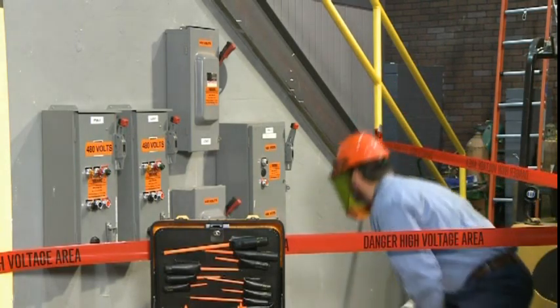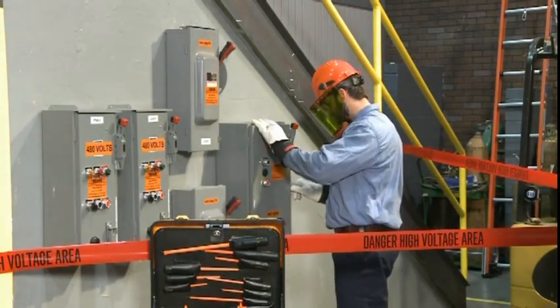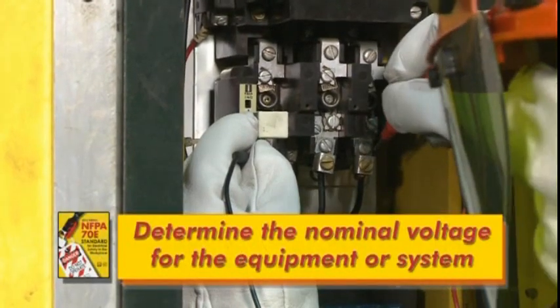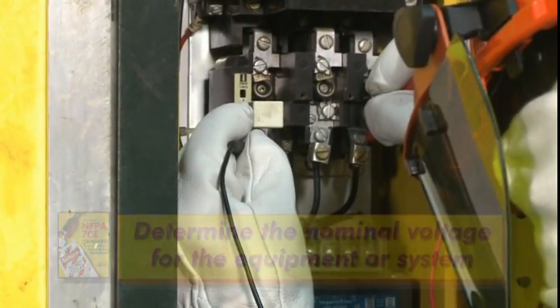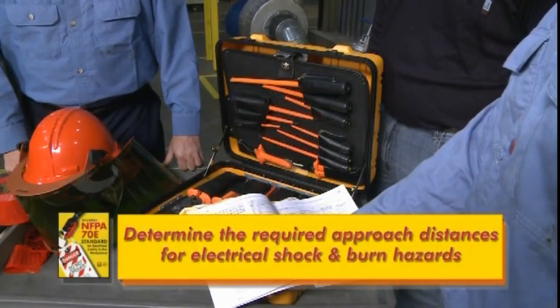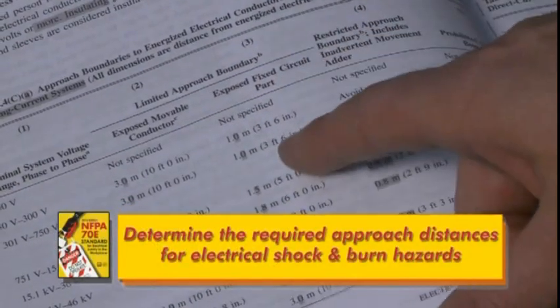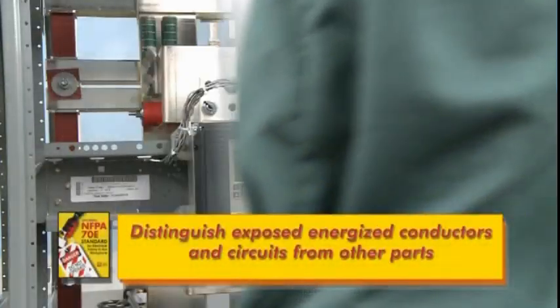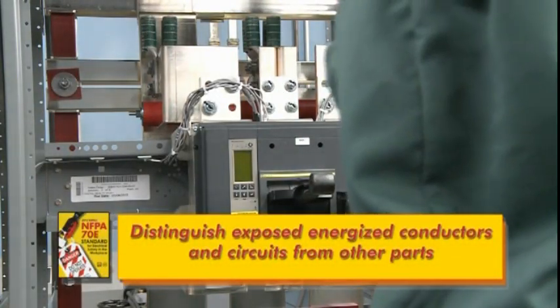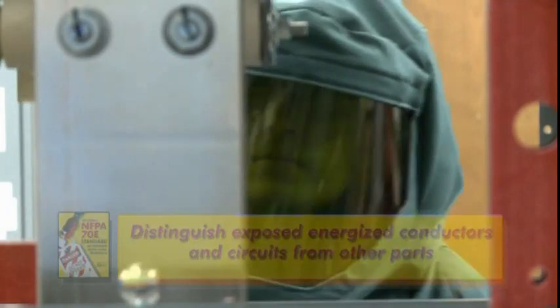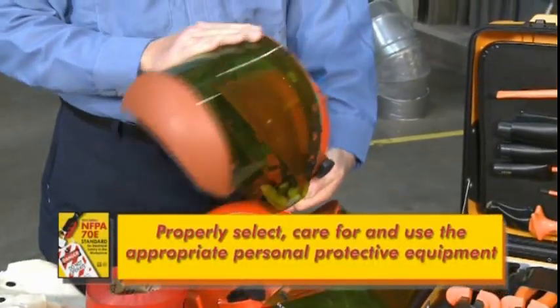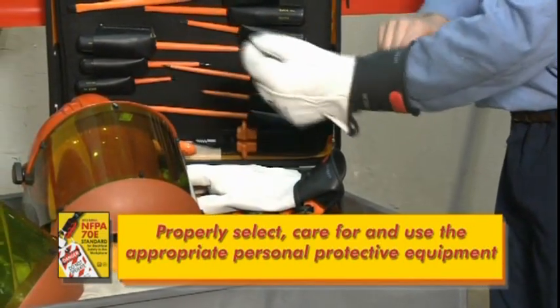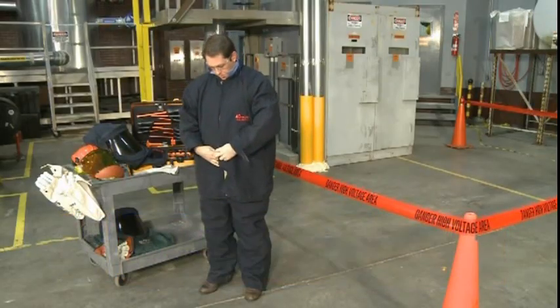Electrical workers who meet this definition of a qualified electrical worker will be able to determine the nominal voltage for the equipment or system, determine the required approach distances for electrical shock and burn hazards, 3 feet 6 inches, distinguish exposed energized conductors and circuits from other parts of the equipment, and properly select, care for, and use the appropriate personal protective equipment for both shock protection and arc flash protection. Being properly qualified is just one of the NFPA's safe work strategies.